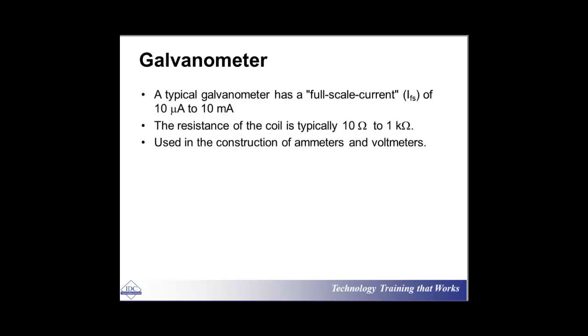And that will give the sensitivity of your equipment. If you have adjusted to something like 10 microamp to 10 milliamp, you have set your equipment to behave very sensitive. If it is between 1 to 10 amp, the sensitivity is very low, but you are measuring very high currents. So if by mistake you set your equipment to measure between 10 microamp to 10 milliamp, and connect it to a source passing something like 10 amp, bang, your meter is gone. You need good judgment before you connect your metering device to the circuit, to understand approximately how much current you're going to measure.